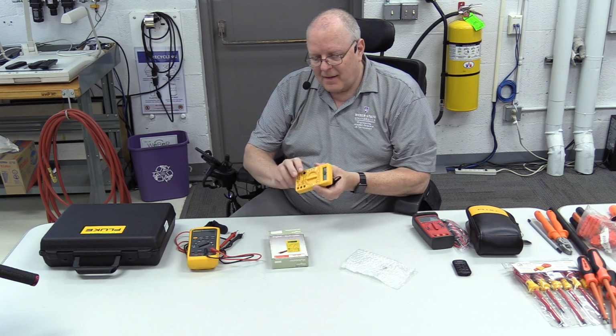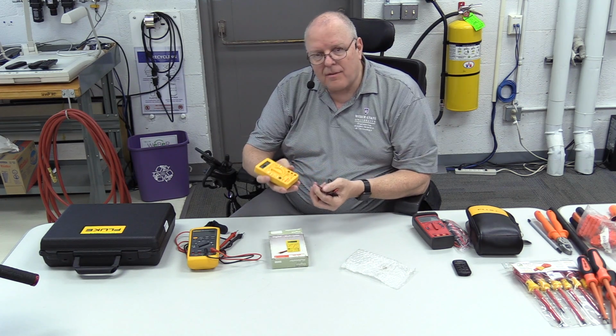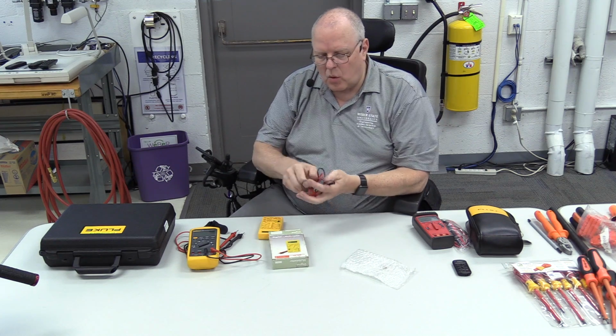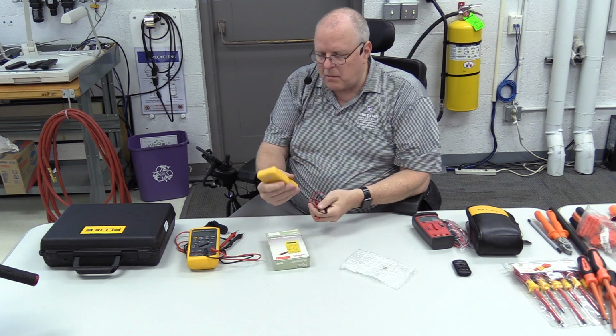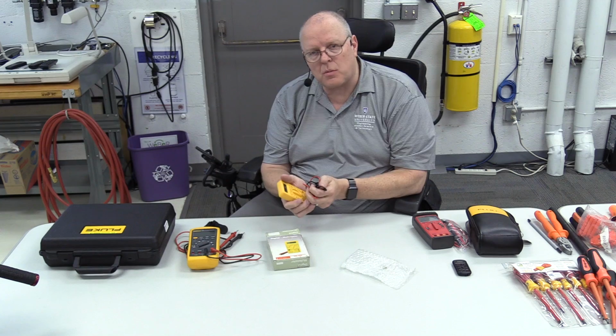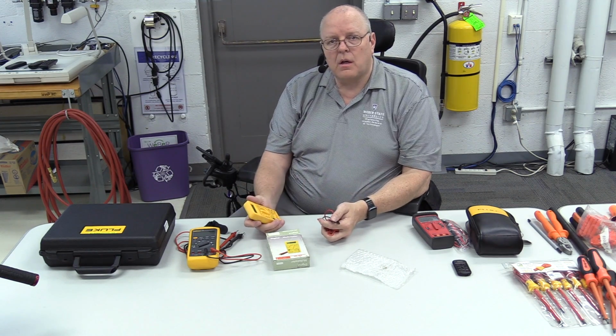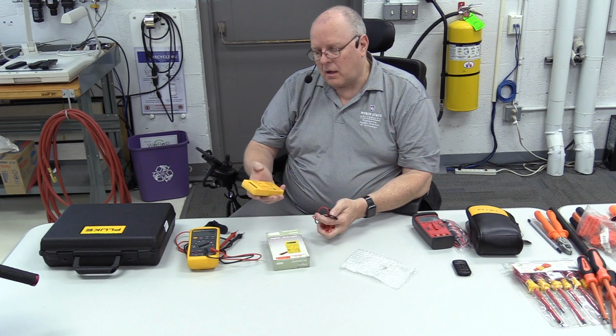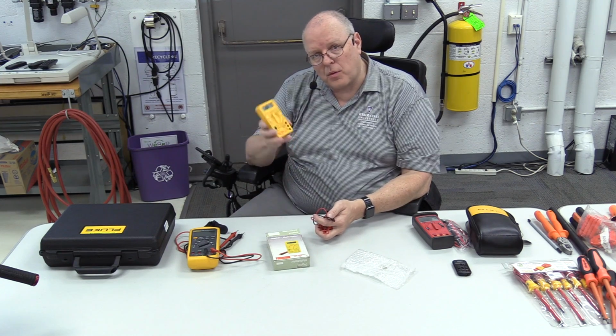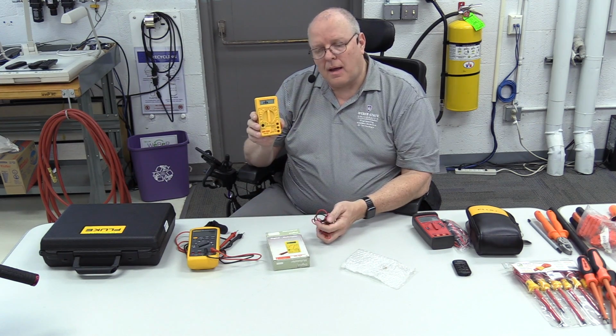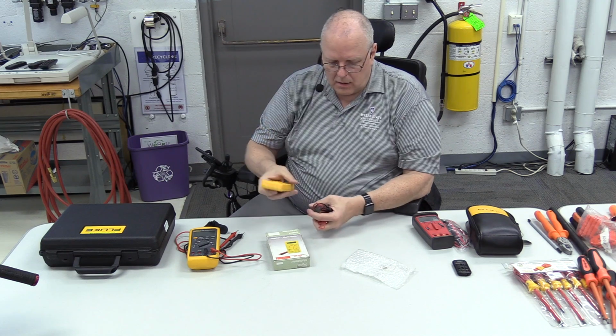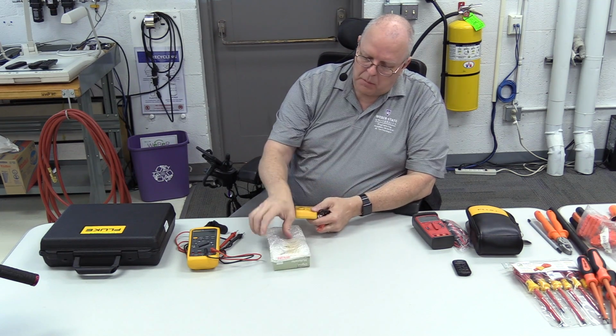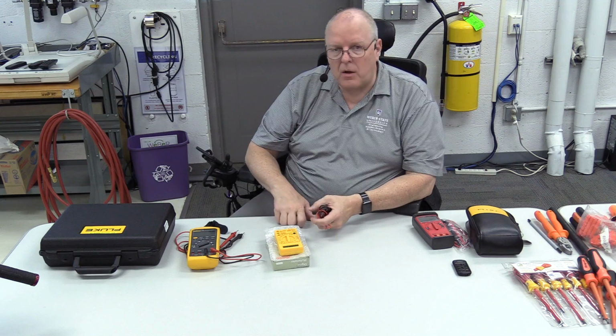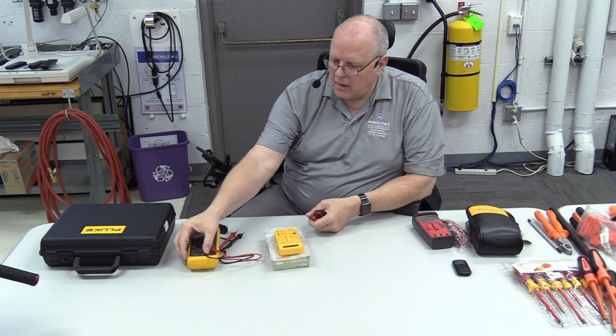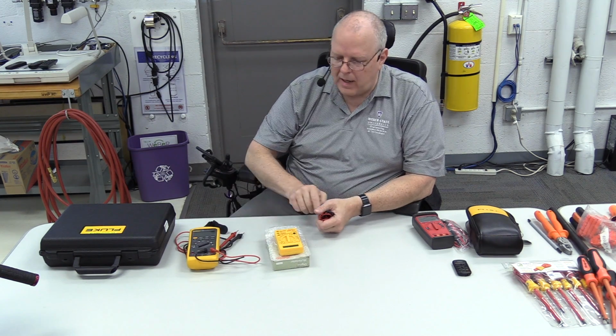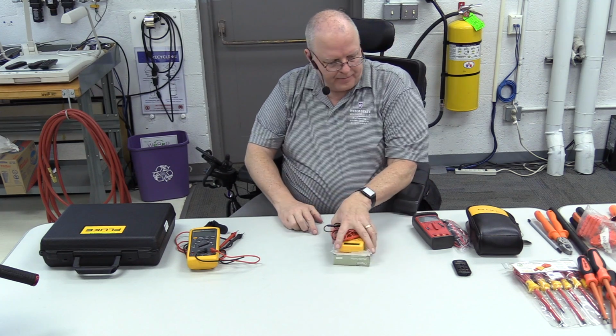So if it doesn't have that rating, that means that just holding the meter leads or the multimeter in your hand while taking a measurement on a high voltage circuit, there's a possibility that it could do damage to the meter or even jump through the case of the meter and shock you. So get rid of the cheap meters. Find yourself a meter, no matter the price, that has a Category 3 rating.